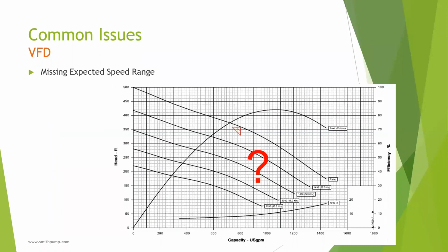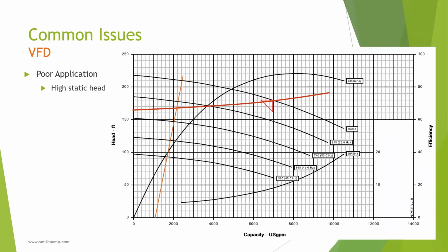Okay, so now we're jumping over to VFD related issues. If possible, provide a system curve and expected operating range so the best pump can be selected. If this information isn't shared, we could pick the wrong pump that still meets the duty conditions specified. VFDs have been marketed as the best way to save energy and reduce operating costs. This is true, but not for every application. It's possible to install a VFD in a poor application for little return on investment.